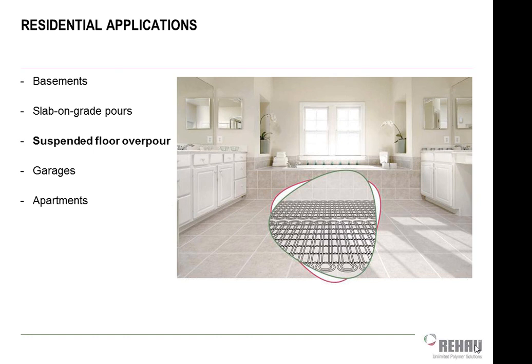You can use this to heat your garage. And there you can have the debate a little bit on whether you want to have a glycol in your system or not. In your garage, you should be fine without the glycol unless you unfortunately leave your door wide open on your garage for long hours at a time. Then you might have to be a little concerned about that. But a lot of garages go in without any glycol in the system.